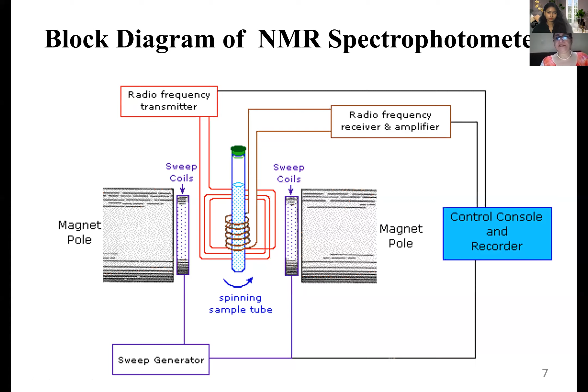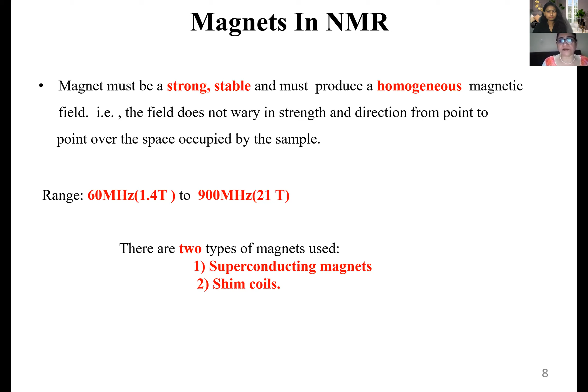Now the magnets, there are two types of magnets in an NMR spectrophotometer. One is a superconducting magnet and the second is the shim coils. The magnets must be strong, stable, and must produce a homogeneous magnetic field. That is, the field should not vary in strength and direction from point to point over the space occupied by the sample. And the range is somewhere from 60 megahertz, that is 1.4 Teslas, to 900 megahertz, that is 21 Teslas. So you have a variety of NMRs available in the market. The greater the strength of the magnet, the more costly is the instrument.